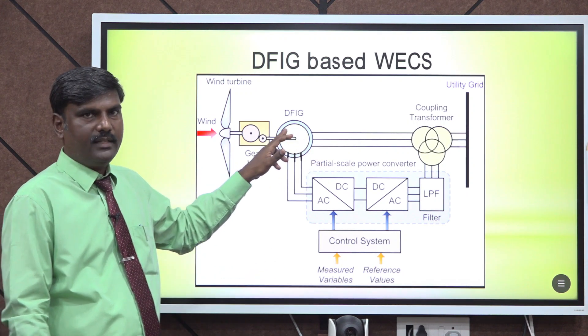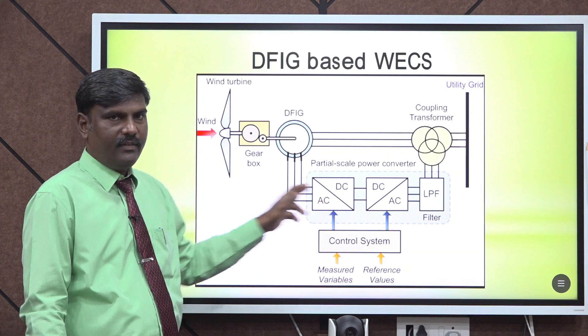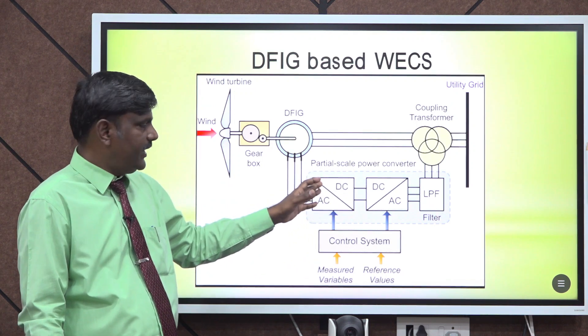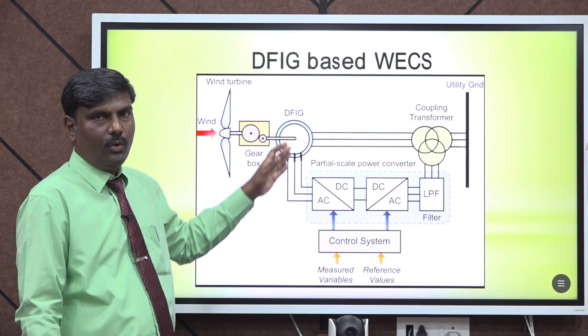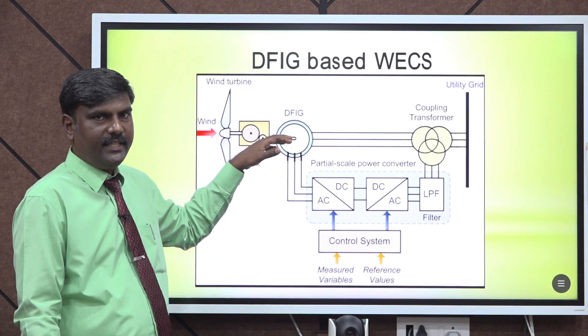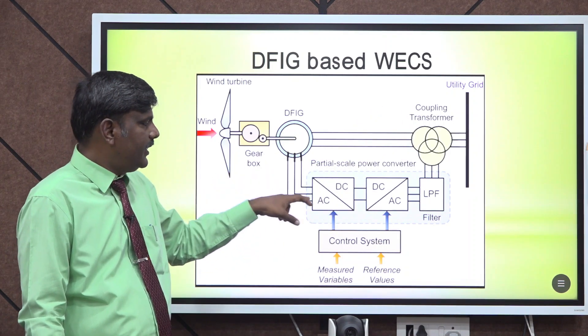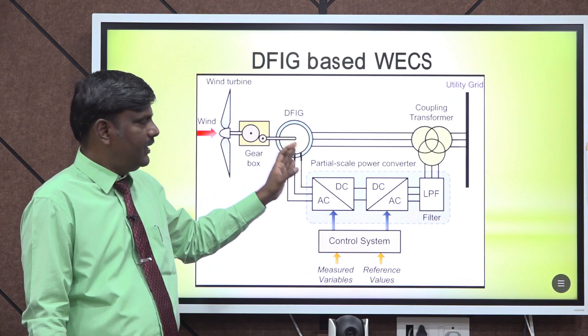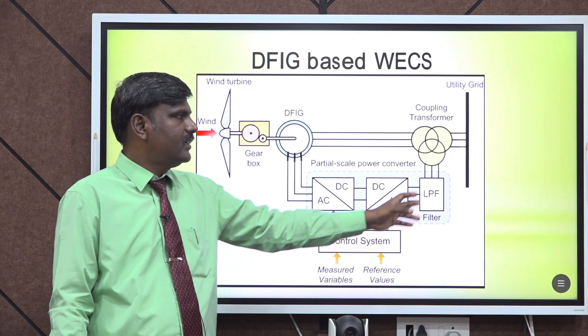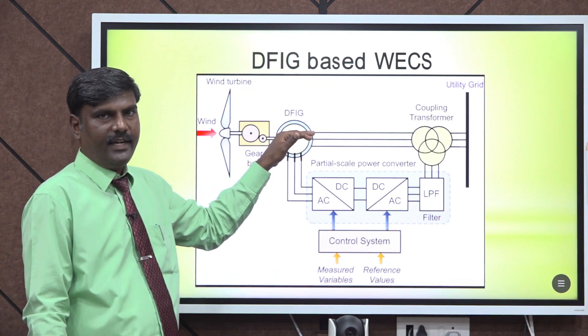To maintain the speed of the rotor as constant, power from the grid is fed to the rotor through these converters — the AC line is converted into DC power and then this DC power is again converted into AC power and it is fed to the rotor of the doubly fed induction generator. If you want to reduce the speed, you can extract the rotor power and deliver it to the grid. The AC to DC converter extracts power from the rotor, converts it into DC, then DC power is again converted into AC and fed to the grid, thereby maintaining the speed of the doubly fed induction generator as constant.